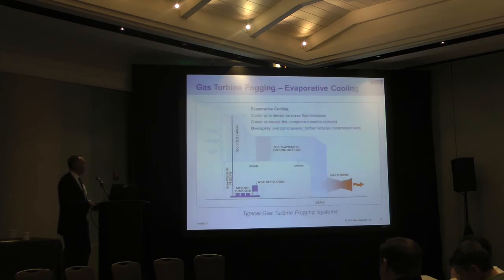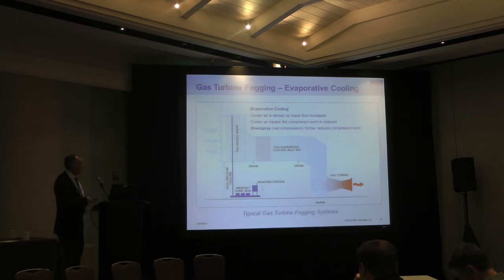The technology is pretty simple and straightforward. It's basically a high-pressure pump skid. We use demineralized water. That's to avoid fouling the compressor blades if water gets in there. There's high-pressure feed lines that go to a nozzle array up in the inlet filter house. And the fog is injected into the airstream and it evaporates as it's carried with the airstream to the compressor inlet. So for evaporative cooling fogging, where people are concerned, mostly OEMs can be concerned about fog entering the compressor. In that case, we inject just enough fog to fully saturate the air, and we try to give it maximum evaporation time so when it comes to the inlet, it's fully evaporated.